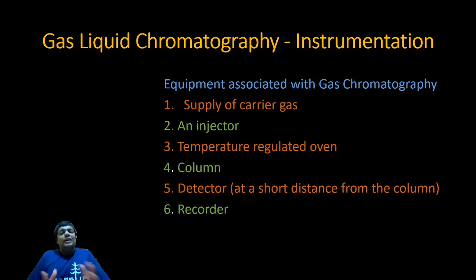Let us start with the first instrumentation picture of gas liquid chromatography. This is a gas cylinder with two different measuring valves filled with gas as a mobile phase. Friends, this first valve will always measure the pressure that is inside the cylinder, and this second valve will always measure the pressure that is going out. From here, it will directly reach the side of the injector port. From the top, you are making the sample go inside. This particular point, which is called the injector, also has an oven covered on it, because the sample you inject will be liquid, but when it enters the injector, it will first get vaporized.